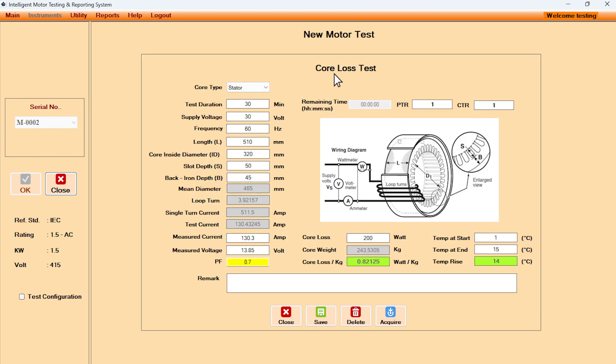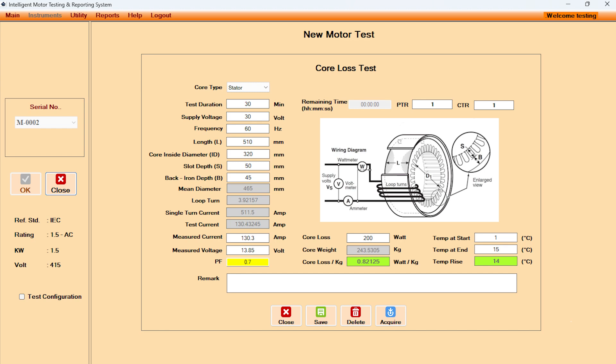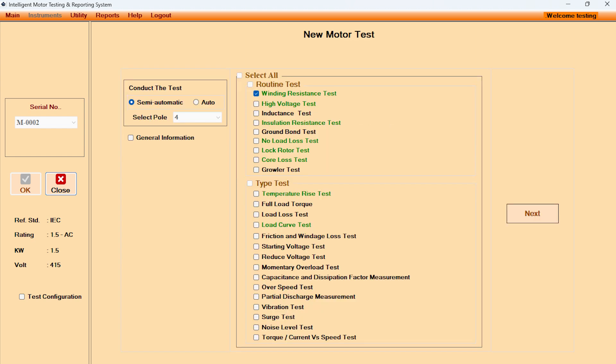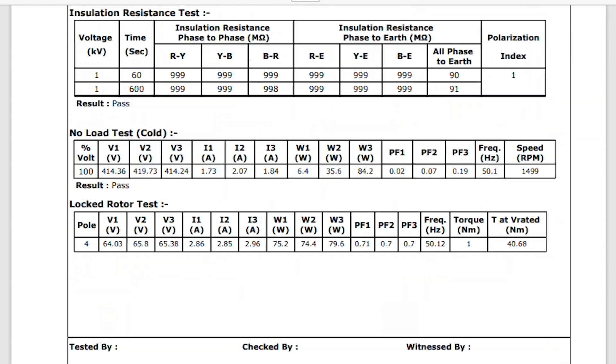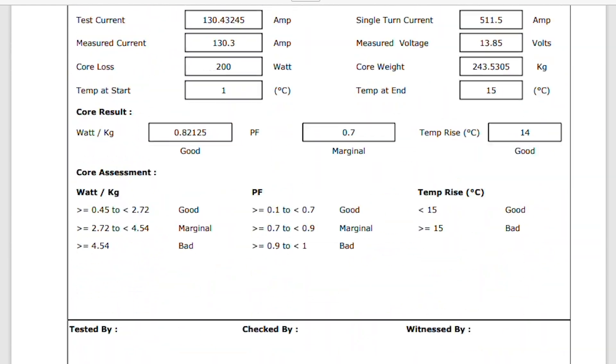Core loss test can be done for both stator and rotor. Software allows user to set good, marginal, and bad assessment, and displays in green, yellow, and red colors respectively. User can conduct all the required tests including torque speed characteristics and then draw a test report instantly.